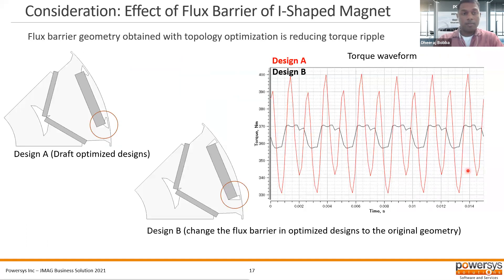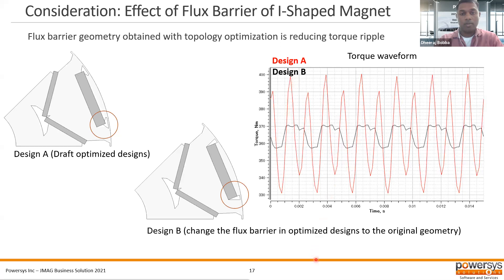Here are the torque waveforms. Once the final geometry is obtained, this is looking at the sensitivity of the shape of those barriers on the top magnet. These are slightly modified, and we can see that the torque ripple reduces further. Design A is the red torque waveform, and design B is the black one. These are things we have to manually check to understand sensitivity to changing those shapes — sometimes we might get even better results.